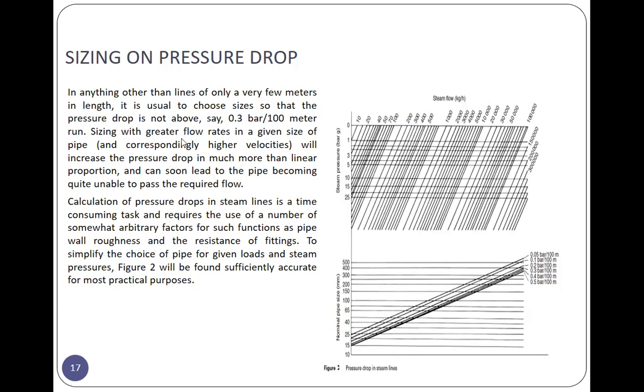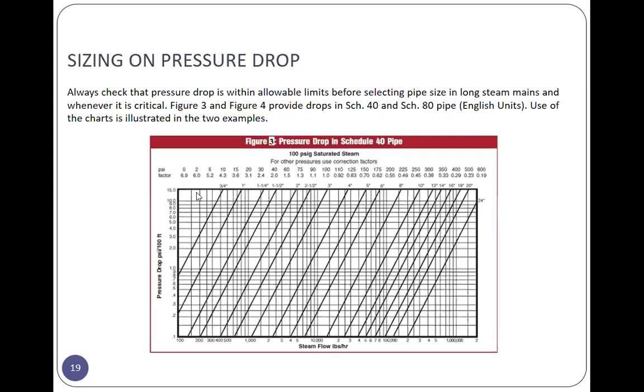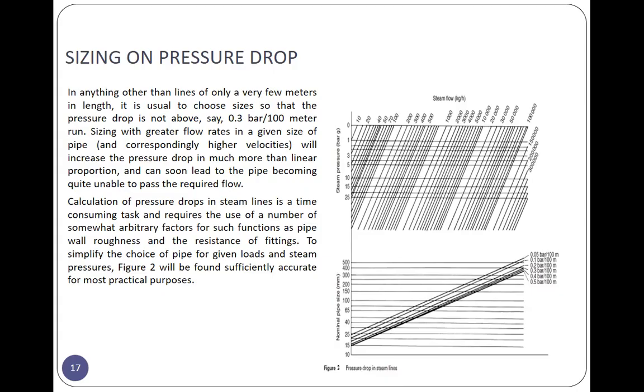So table. Sizing with greater flow rate in a given size of pipe and correspondingly higher velocities will increase the pressure drop in much more than linear proportion and can soon lead to the piping becoming quite unable to pass the required flow. So calculation of pressure drop in steam lines is a time-consuming task and requires the use of a number of somewhat arbitrary factors such as pipe wall roughness and the resistance of fittings. To simplify the choice of pipe for a given load in steam pipe pressure, figure 2 will be found sufficiently accurate for most practical purposes.